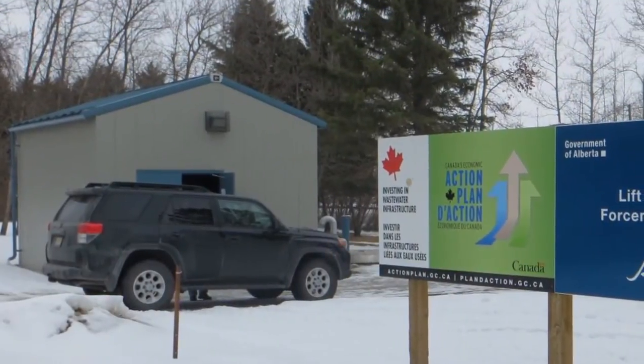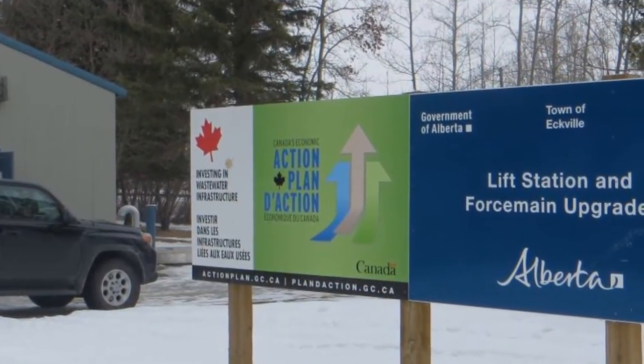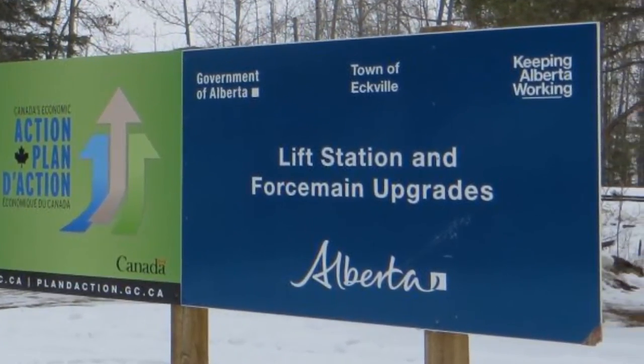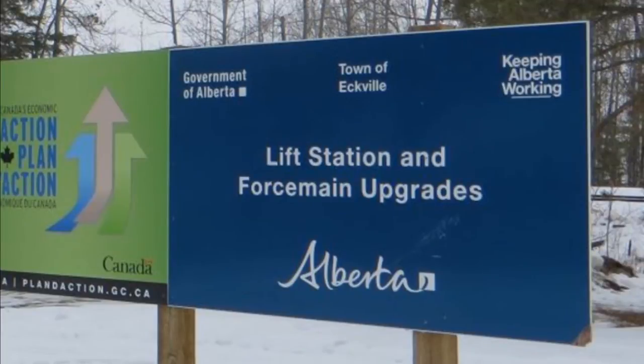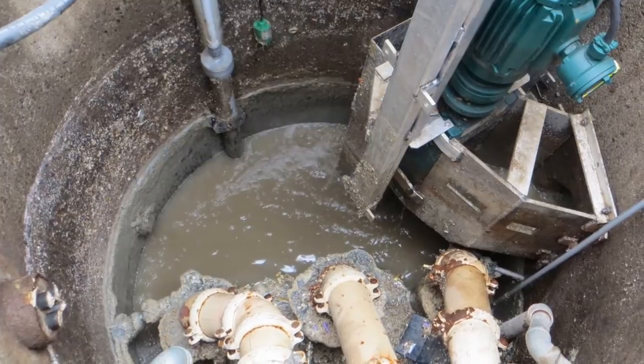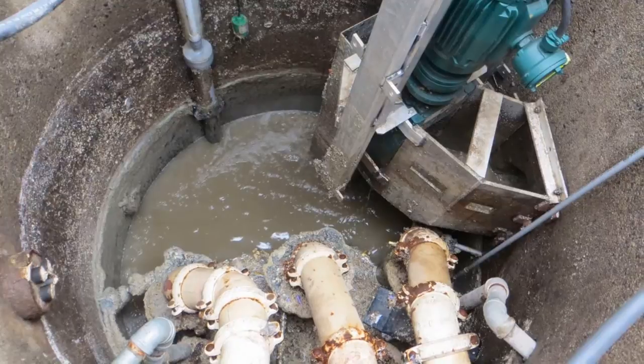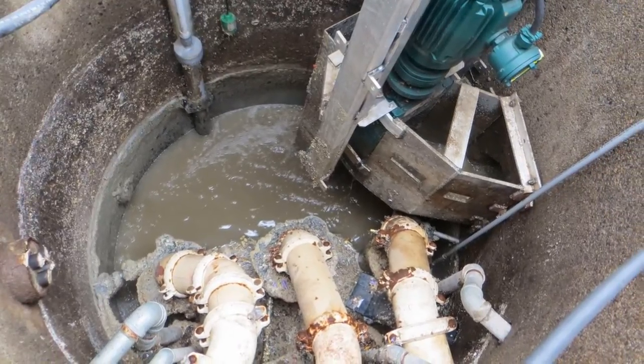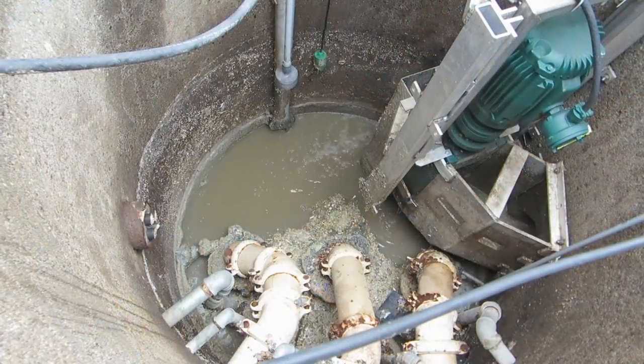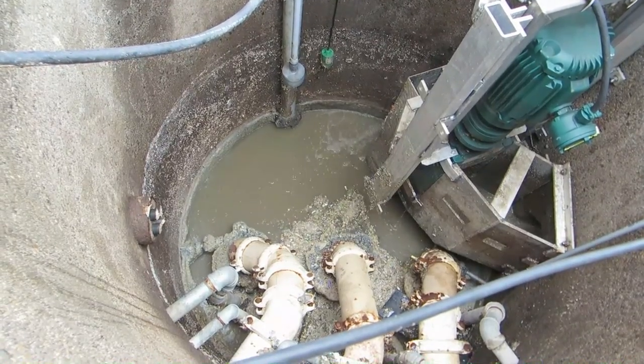Serving a population of 1,100 people and two schools, the town of Eckville completed a sewage lift station upgrade project with startup of the new system in 2011. For level control in the two new pump stations, Greyline PSL 5.0 pump station level controllers were specified. Non-contacting ultrasonic sensors monitor water levels in the wet wells, and the instrument activates pump on and off set points according to the water level.